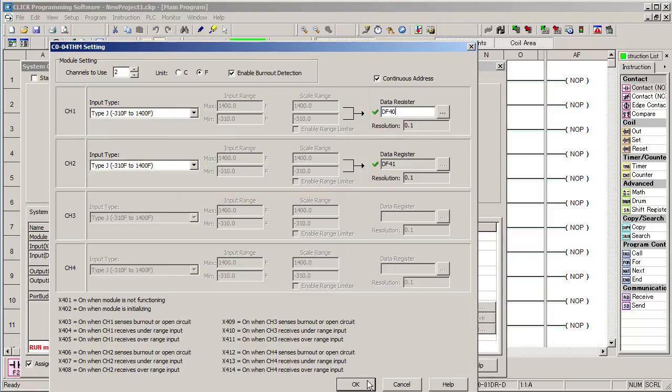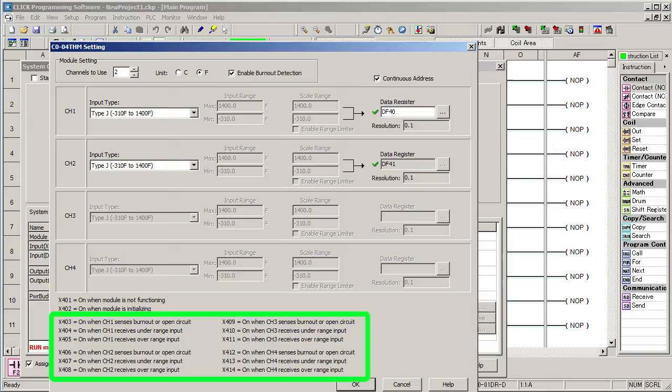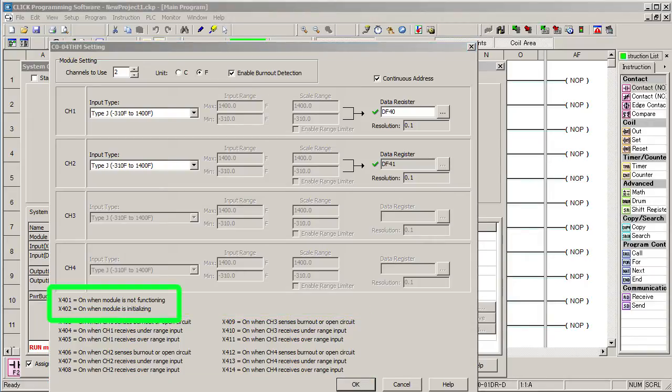This thermocouple module provides indications at these input values to determine if the sensor is open or under or over range. And you can detect when the module is initializing or not functioning. Those are awesome features to take advantage of in your ladder code.